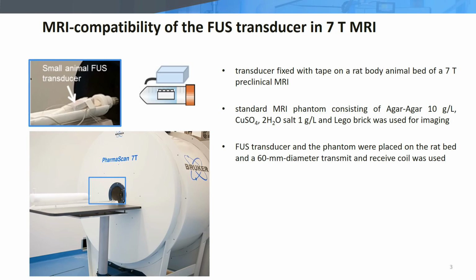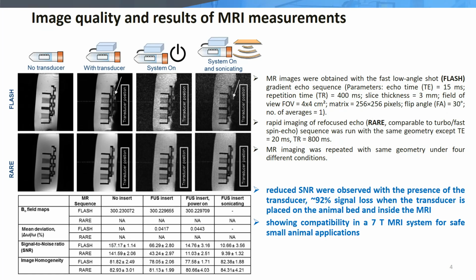For testing the transducer in the preclinical MRI, the transducer was fixed with tape on the rat animal bed of a 7 Tesla Bruker MRI, together with an imaging phantom. After adding the coil, the whole setup was inserted into the bore. MRI compatibility measurements included field mapping of the static magnetic field B0 and acquisitions with multiple pulse sequences, RARE and FLASH.